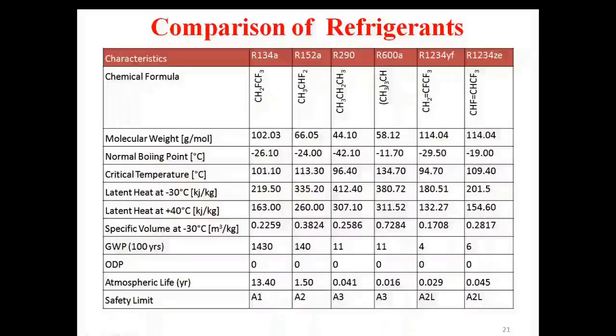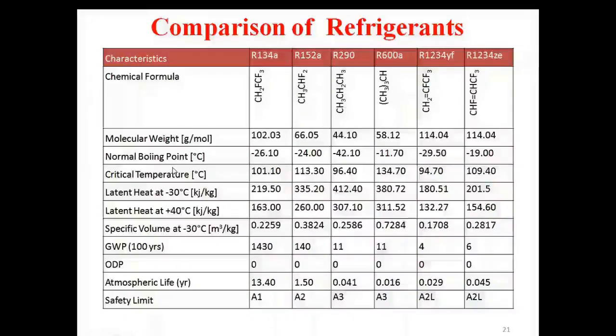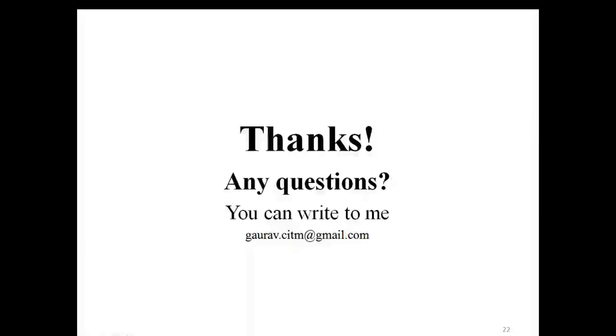Next is comparison of refrigerants. We have compared different properties such as molecular weight, normal boiling point, critical temperature, latent heat, specific volume, GWP, ODP, atmospheric life, and safety group. For example, the normal boiling point for R134A is −26.1°C, meaning it will start boiling at this temperature at atmospheric pressure. Thank you. Any questions can be written to gorg.catem@gmail.com.